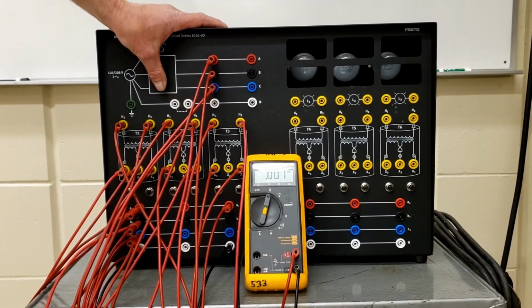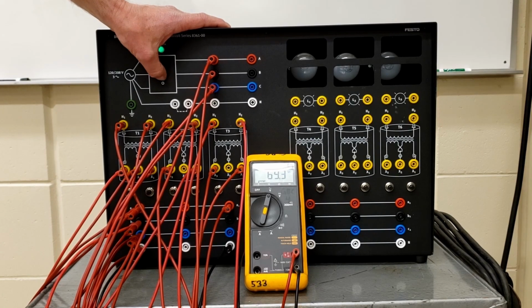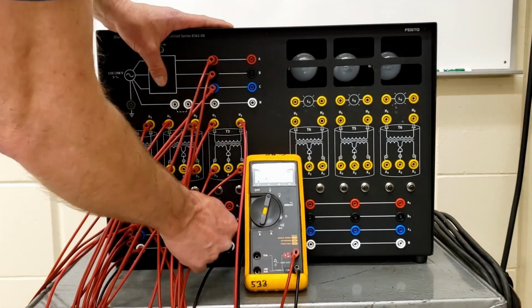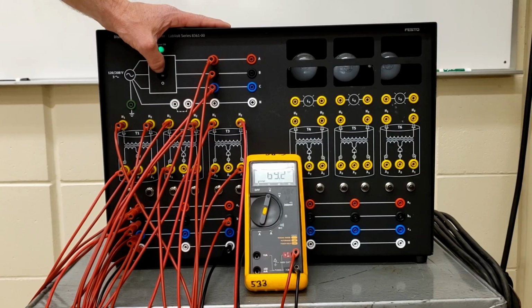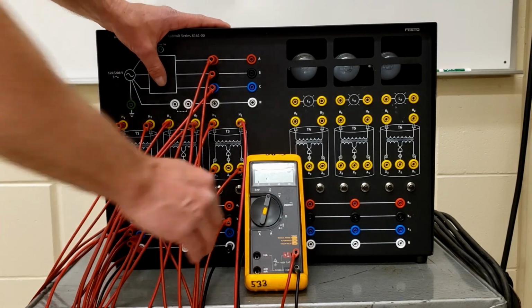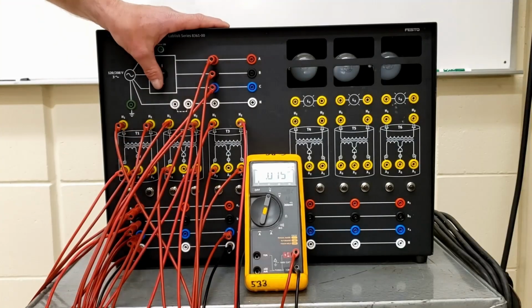So A on the secondary and neutral should be 70 volts. Beautiful, we got 69.3, basically 70 volts. Okay, between B and neutral, we should have 70 volts, which we do, 69.2. Okay, and let's take a look at C and neutral and see whether it's the same or whether it's higher. C and neutral is 120 volts.